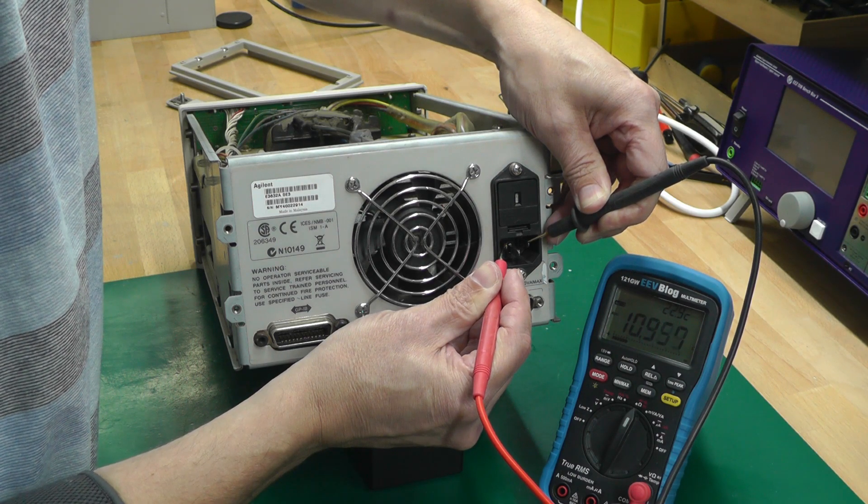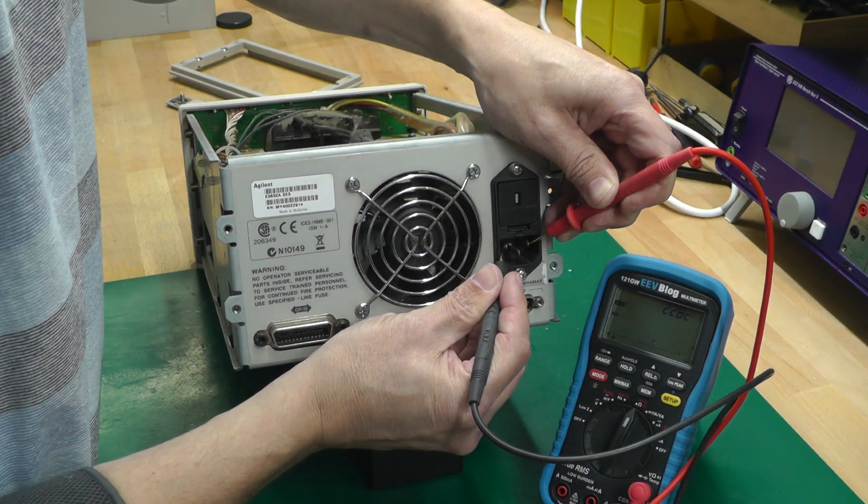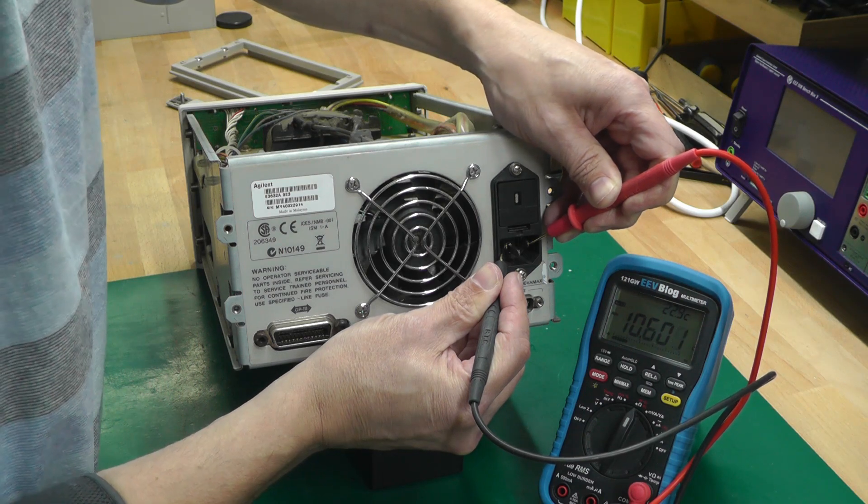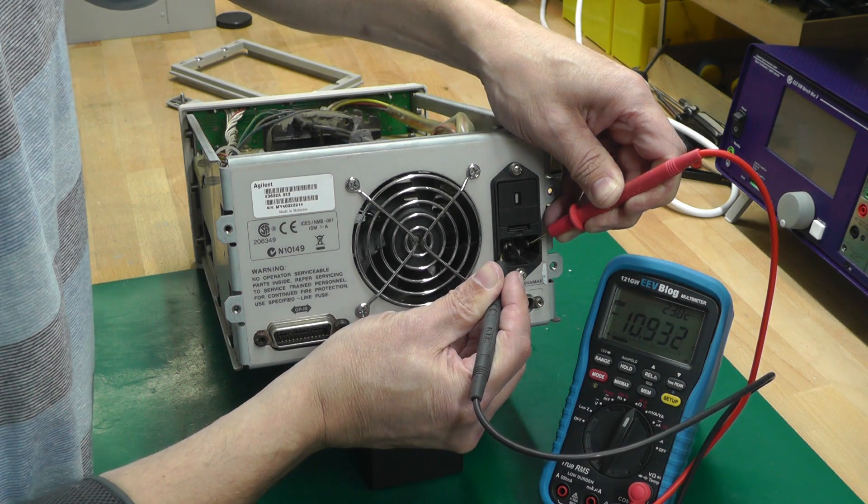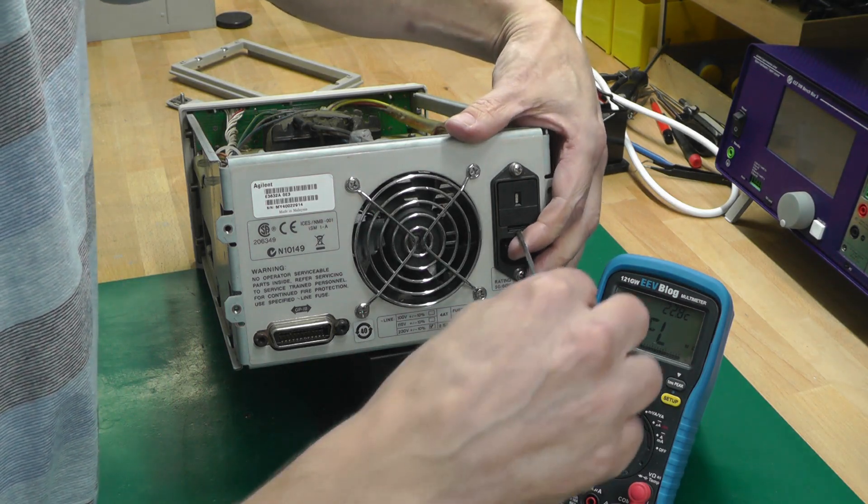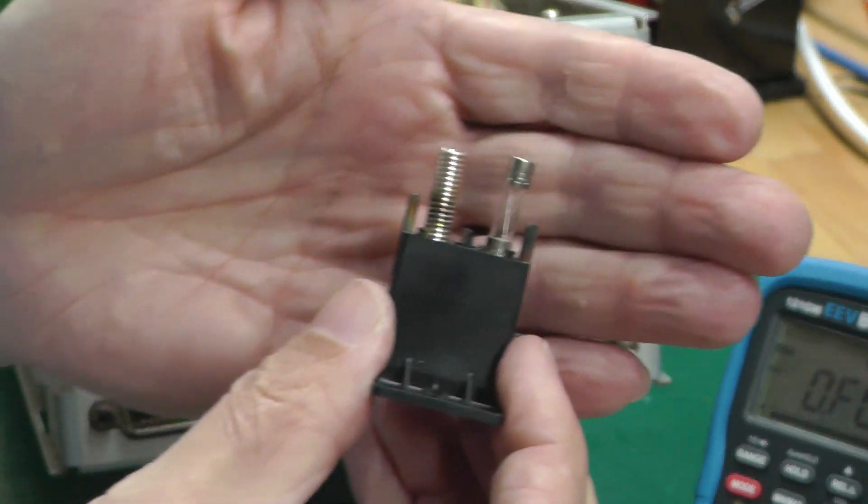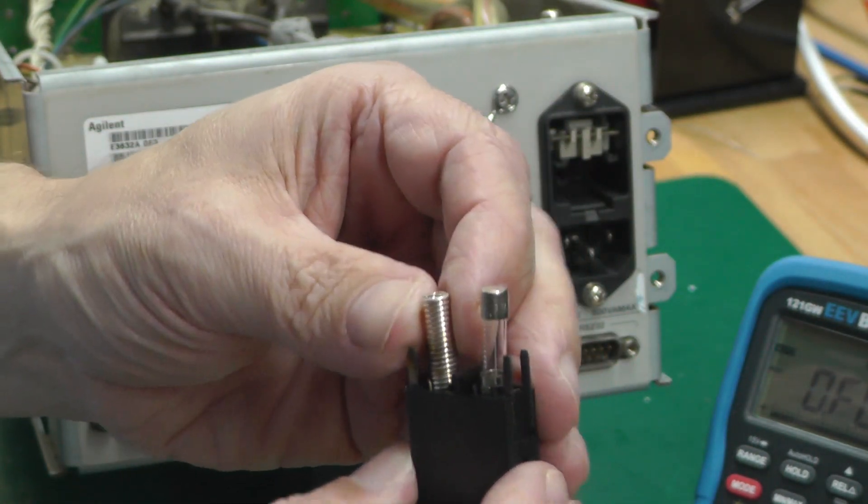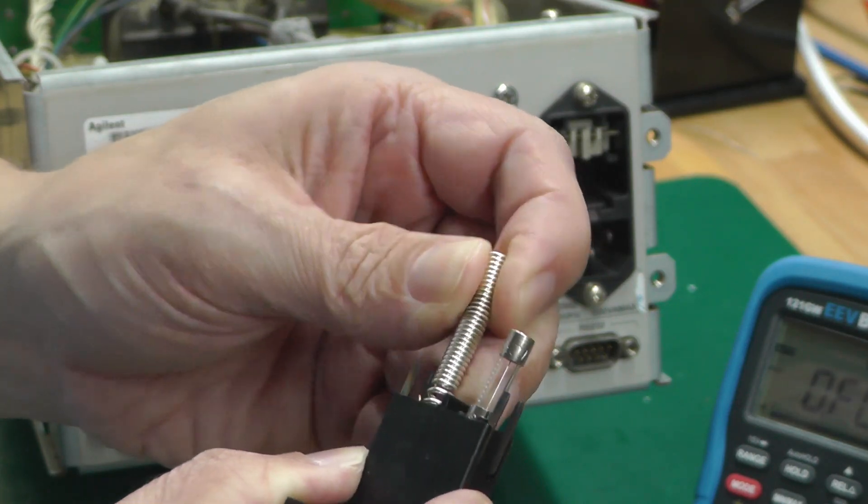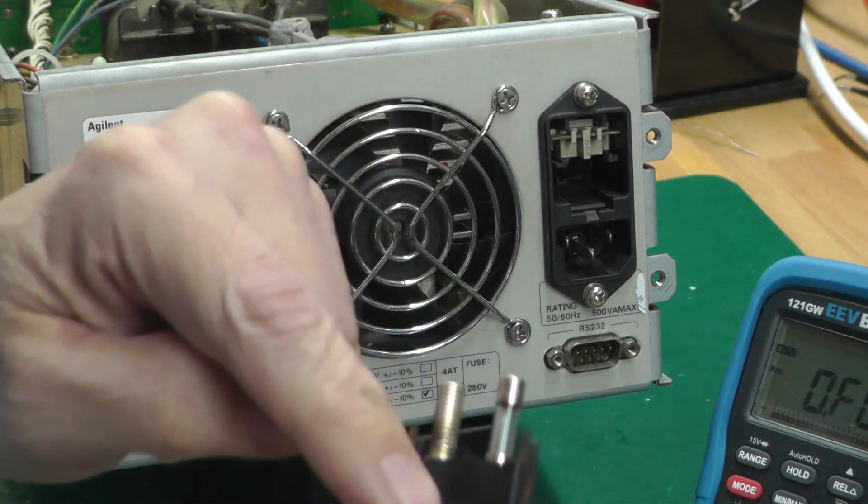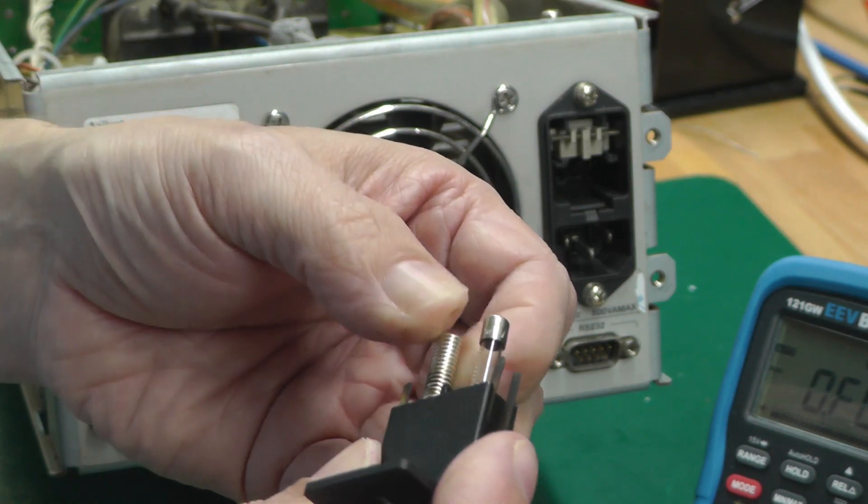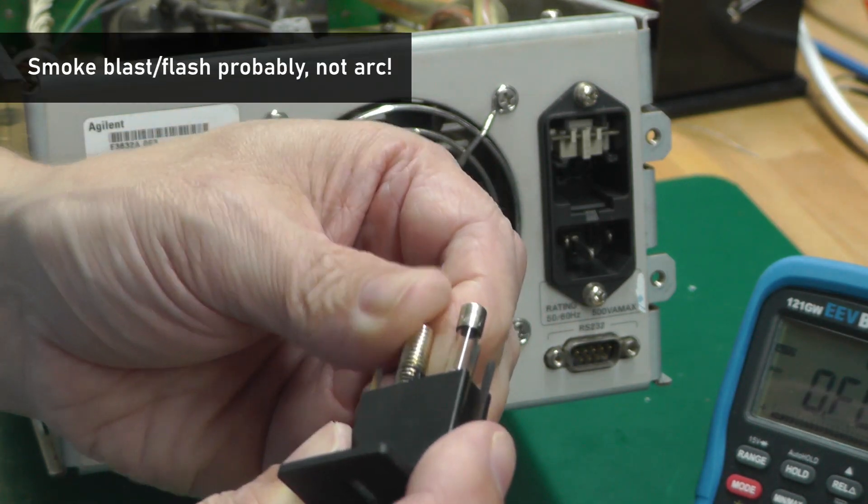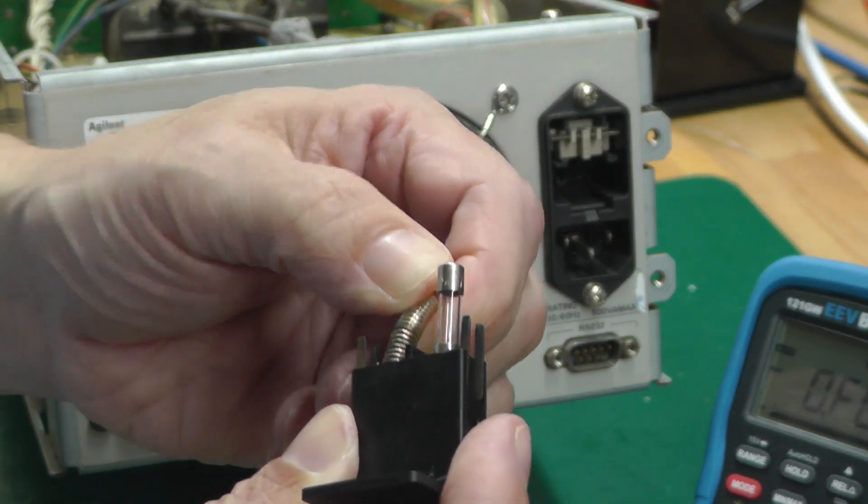11 ohms. What's going on there? Something weird. That was 200 before. So on here we've got the little fuse carrier, but it's also got this little coil of wire. It is a bit discolored. Something's been arcing there. I think that's probably from a blowing fuse at some point and it's arced right across, discolored that there.